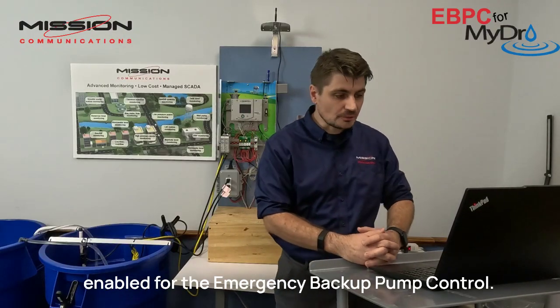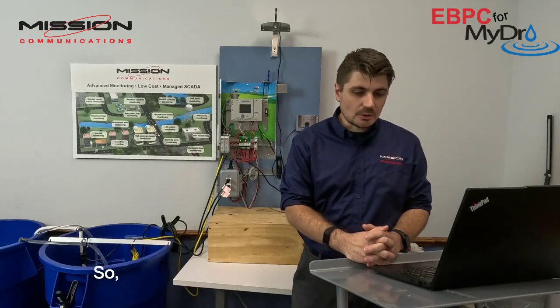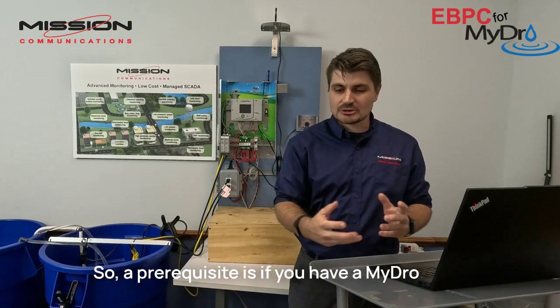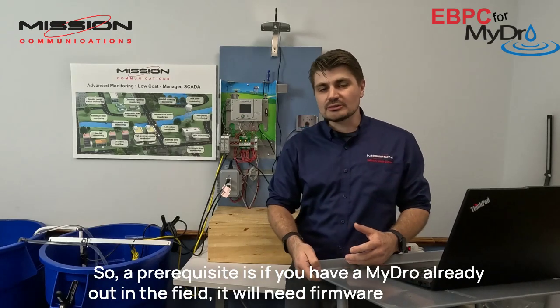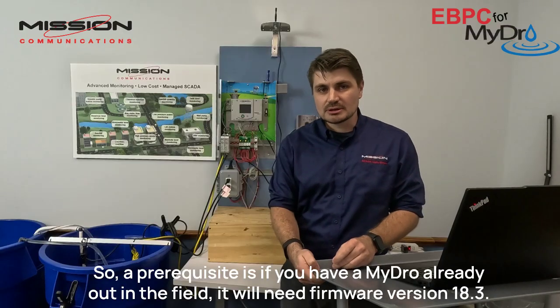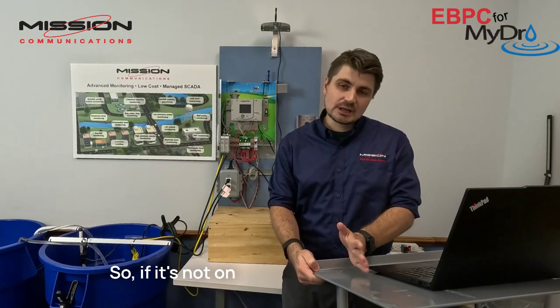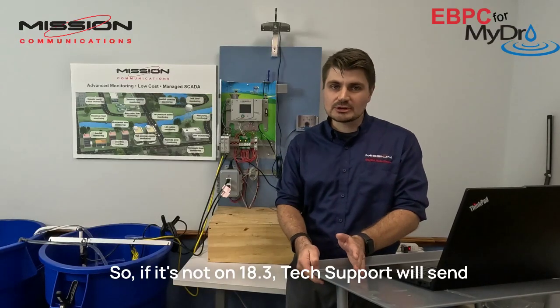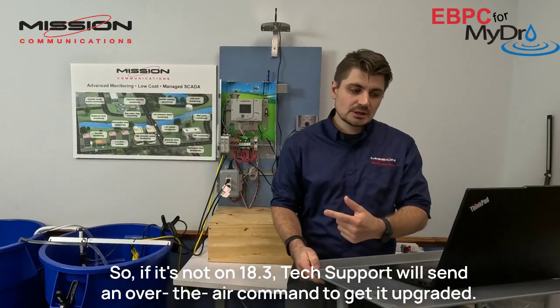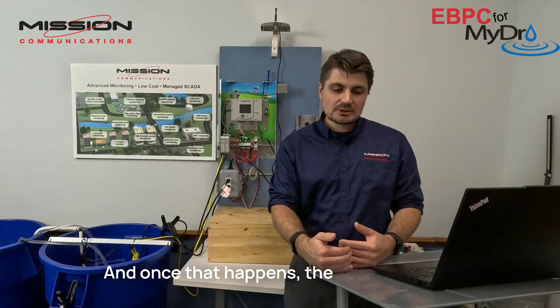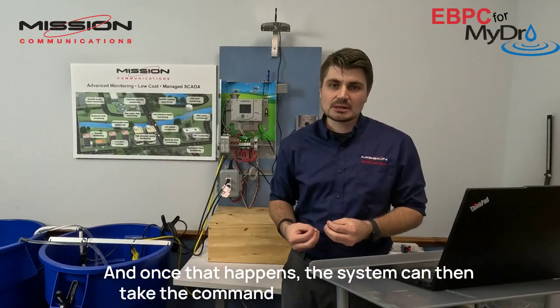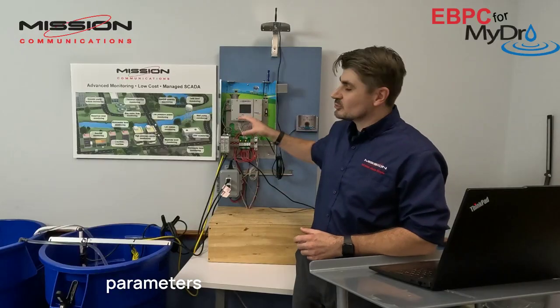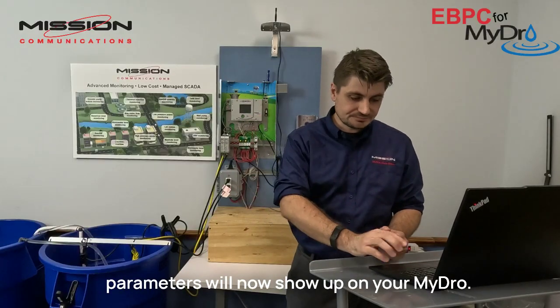So a prerequisite is if you have a MyDro already out in the field, it will need firmware version 18.3. So if it's not on 18.3, tech support will send an over-the-air command to get it upgraded. And once that happens, the system can then take the command and the configuration parameters will now show up on your MyDro.